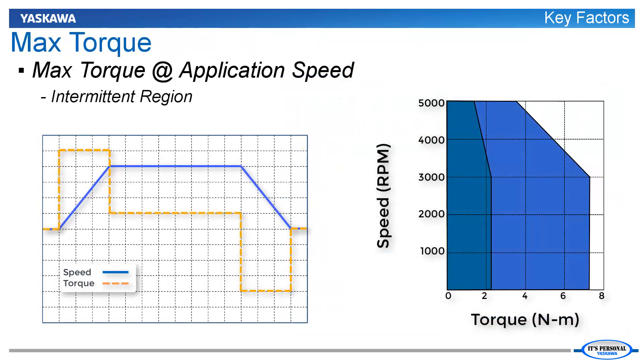It is important to ensure that the motor can produce the required max torque at the application speed. The max torque at application speed ideally falls within the intermittent region of the motor's speed torque curve. It can also fall within the continuous region, but this may be an indication that the motor is oversized.